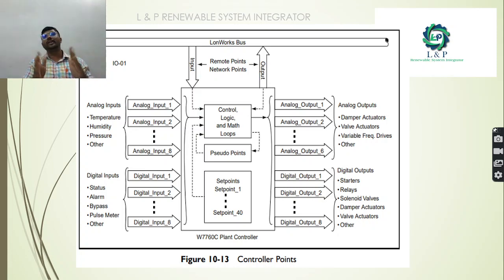And most importantly, with the controller we will be connecting so many digital inputs. It can be a status or an alarm, bypass, pulse meter, anything, okay. And also we are providing some commands through the controller. It can be a digital command, it can be a starter, relay, solenoid valve, damper actuators, valve actuators, it can be anything, okay. And if you're getting an analog input module, it can be a temperature sensor, a humidity sensor, or a pressure sensor also. If you're going for analog output, it can be a damper actuator, valve actuator and variable frequency drives.